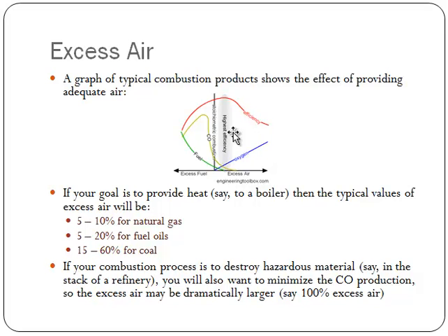But if you look at the efficiency, so how much heat is being provided by this, and again, this is something that we will be discussing how to compute in a few more lessons, then the efficiency is going to increase as I add fuel or add air, but at some point, now I'm just really spending a lot of time heating up that extra oxygen and nitrogen, and my efficiency will decline.